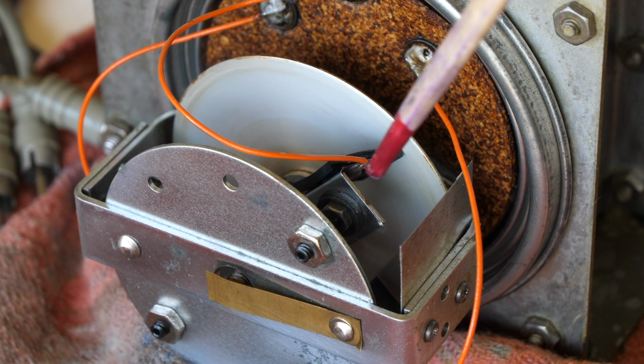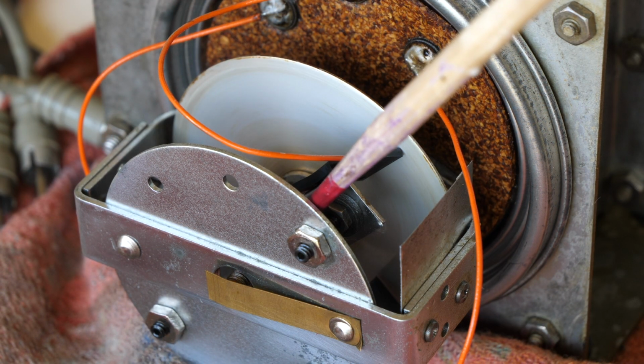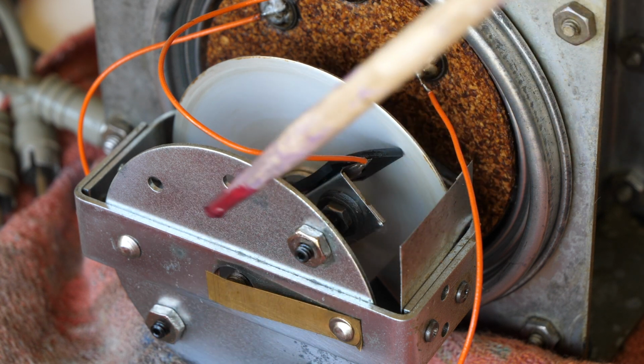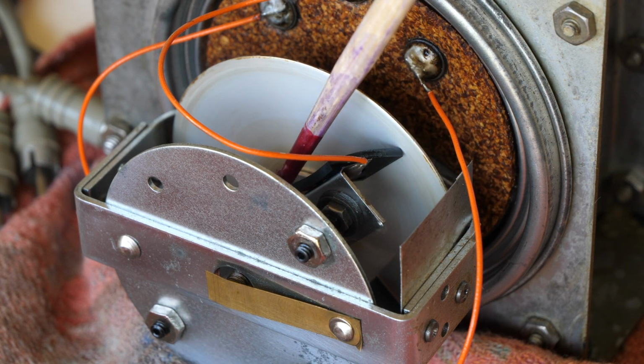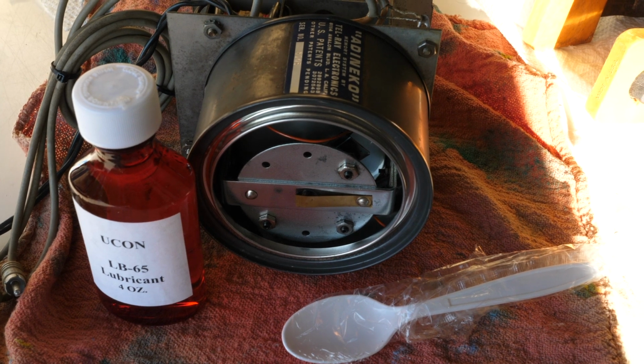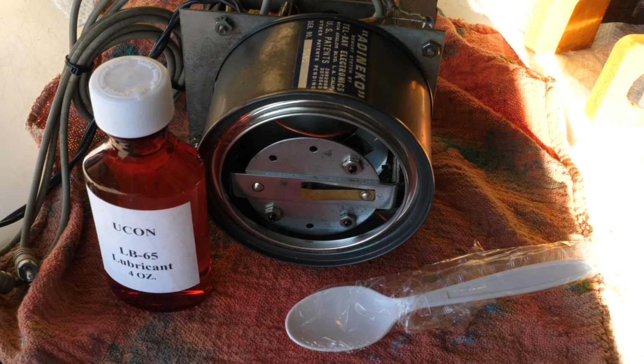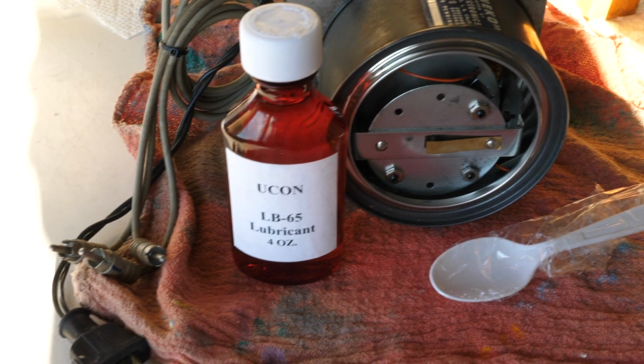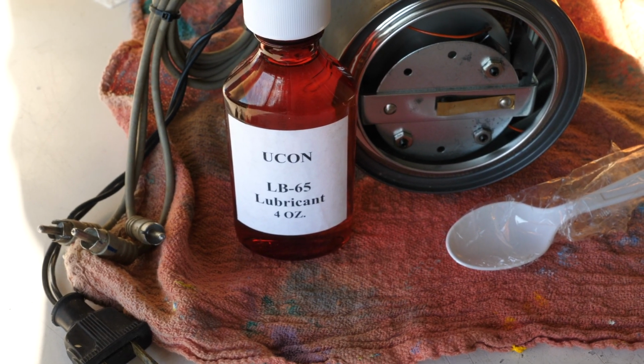The internal components have all been thoroughly cleaned with alcohol. Then I applied a light coat of the LB65 oil. The can has been reattached using C-clamps. We're going to add 2 tablespoons of the LB65 lubricant into the can. I've powered on the motor. As you can see, the disc is spinning inside. And we have good contact of the wiper to the disc.